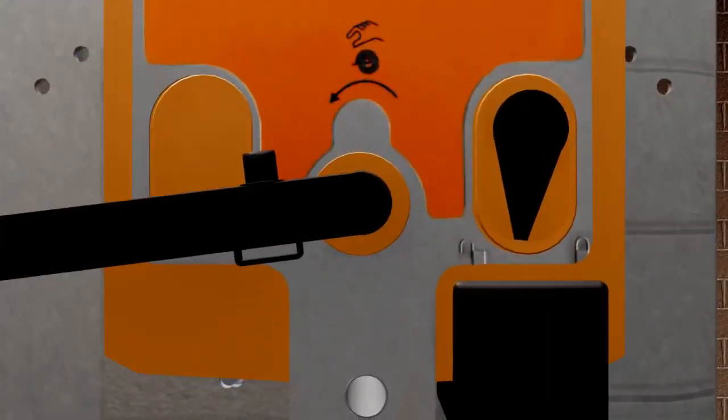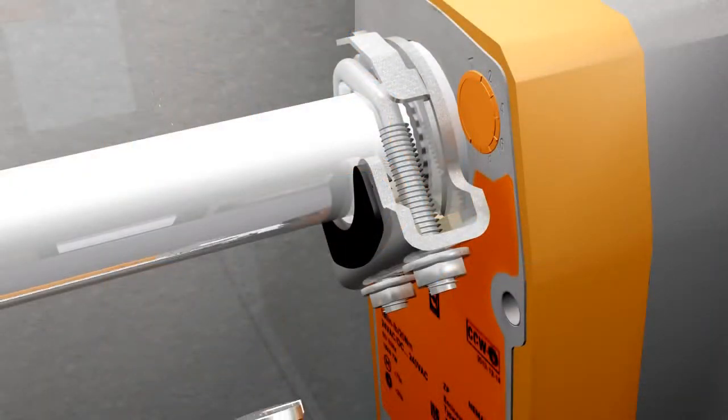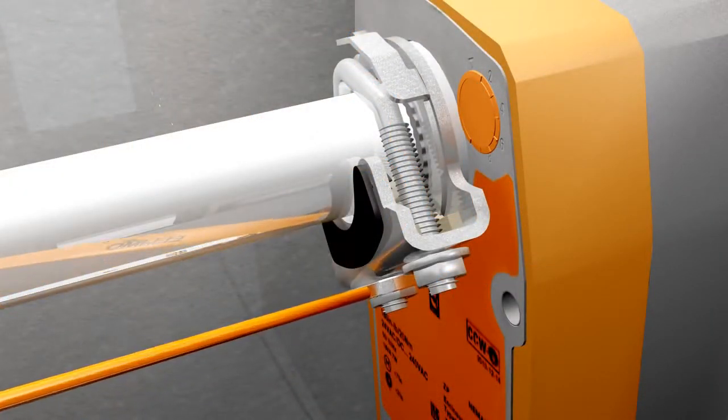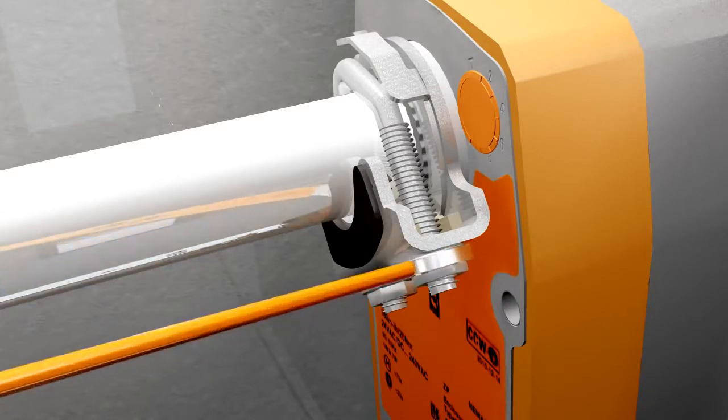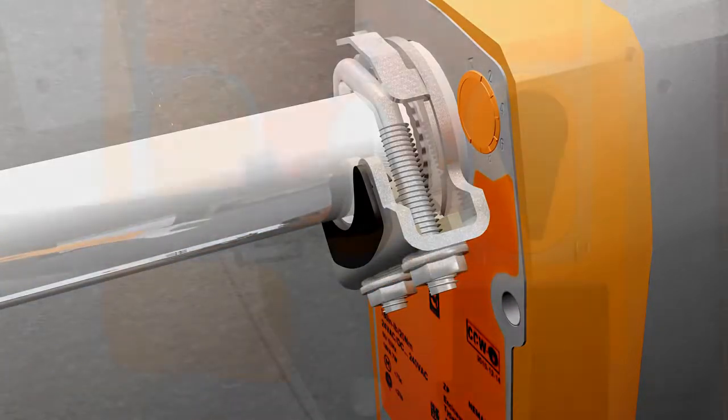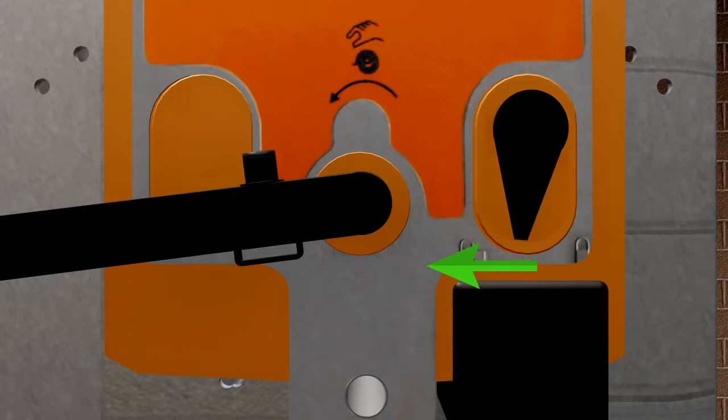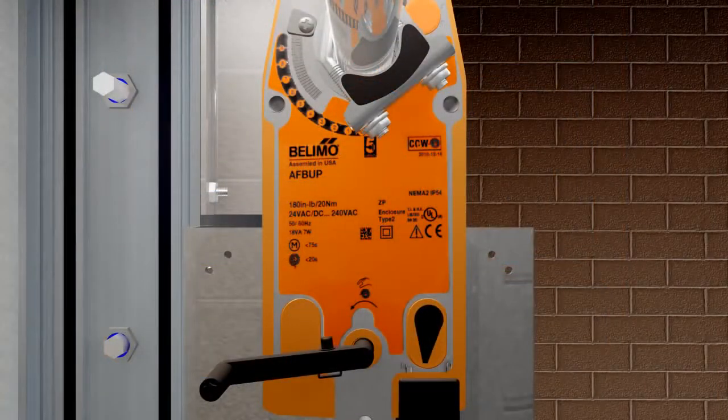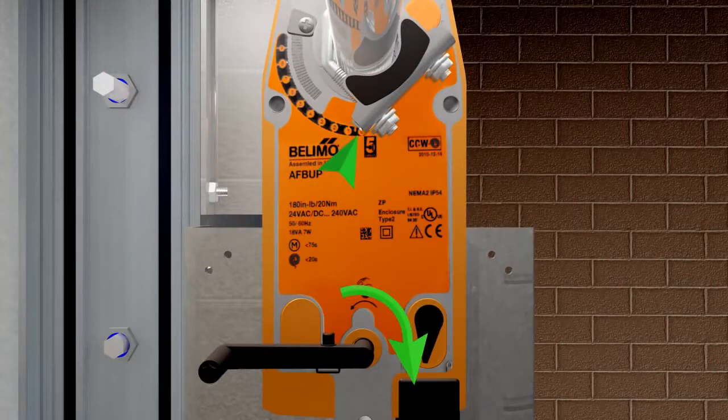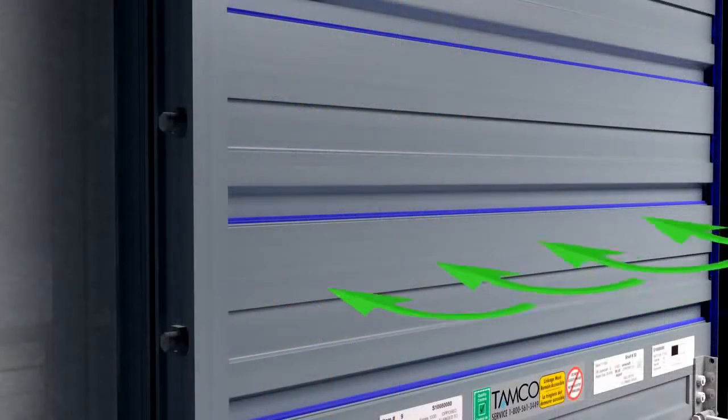Lock the universal clamp in place by toggling the manual override lever to the locked position. Firmly tighten the V-bolt nuts using a 10 mm wrench or socket. When the manual override mechanism is released, the actuator will automatically drive toward the full fail-safe position. This provides compression against damper gaskets for a tight shutoff.